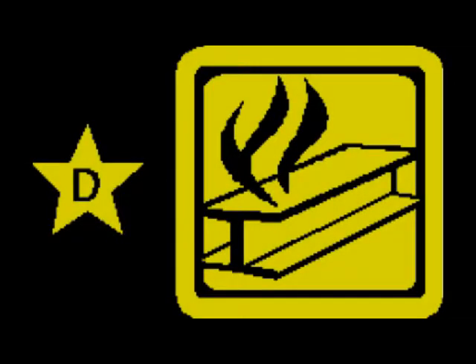D extinguishers are assigned the shape of a star and the color yellow. The icon depicts a metal I-beam with flames above it. Because fires involving combustible metals are most often found in manufacturing facilities, these types of extinguishers are not common to most people. In addition, the high reactivity of flammable metals makes them especially dangerous, and they require additional training to be used properly.